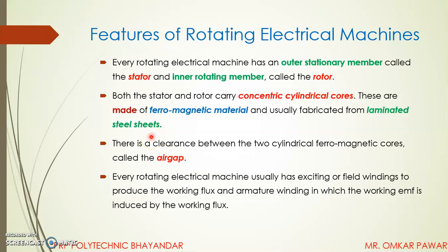So why laminated steel sheets? In order to reduce eddy current losses. By lamination we reduce the area, which increases the resistance of that particular core. If we increase the resistance, then there is less eddy current. So in order to reduce that current we use laminated steel sheets.